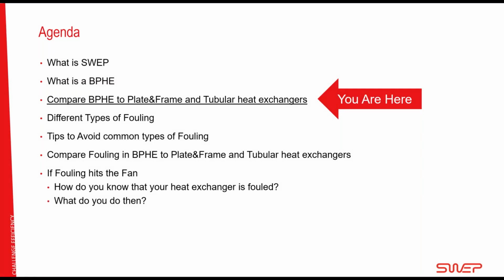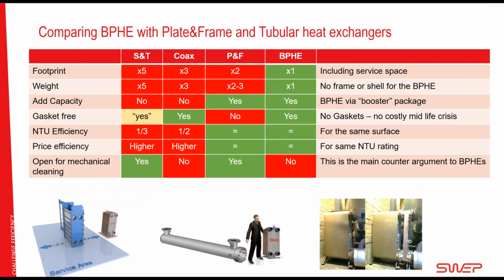So let's compare the brazed plate to other heat exchanger technologies. What I'm trying to show here is, I am biased without a doubt, but I'm trying to show the pros and cons of the brazed plate, the plate and frame, coaxial heat exchanger, and shell and tube heat exchanger. When it comes to footprint, the BPHE is absolutely the winner compared to the coaxial and shell and tube that require much more space. The brazed plate also wins over the plate and frame, since the plate and frame needs a service area to be able to open it when they have to change gaskets.